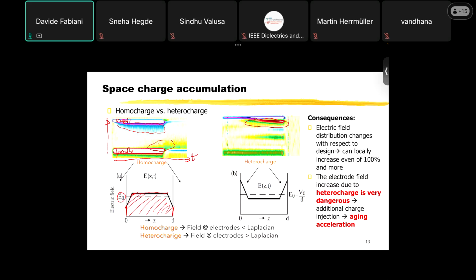The problem is that this increase at the electrode-insulation interface is very dangerous because it can lead to more injection of charge into the material, since charge injection is field dependent. If the field increases due to heterocharge, more charge gets injected, further distorting the electric field. This process can quickly lead to cable insulation failure, so heterocharge is very, very dangerous, while homocharge is not as dangerous.